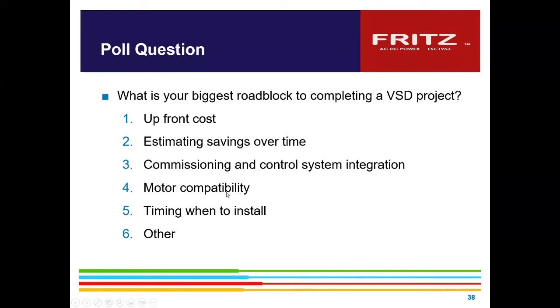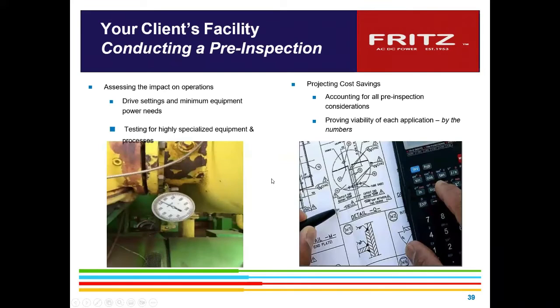And then we also check motor compatibility to make sure it is good. If it isn't, we can recommend upgrading some of the motors to the right thing. And then we can get it installed in a timely way. A lot of people say, okay, I'll put a few VFDs in. Well, you really don't see that incremental change in your total power bill as quickly as you do when you do a complete review of your facility and get that value figured out. So you want to take some time and assess those individual applications. Where is it on flow? Where is it on pressure?